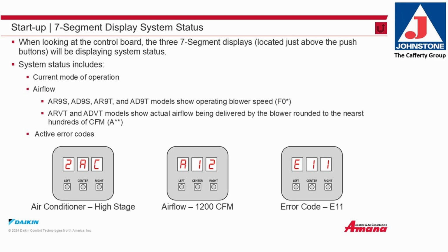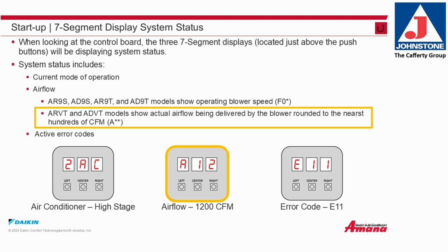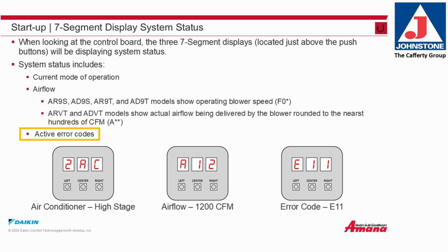Startup using the 7-segment display system status. When looking at the control board, the three 7-segment displays located just above the push buttons will be displaying the system status. System status includes current mode of operation and airflow. The AR9S, AD9S, AR9T, and AD9T models show operating blower speed. The ARVT and ADVT models show actual airflow being delivered by the blower, rounded to the nearest hundreds of CFM. Some operational information and active error codes displayed on the three 7-segment displays would include 2AC, air conditioner high stage; A12, airflow 1200 CFM; E11, error code 11.